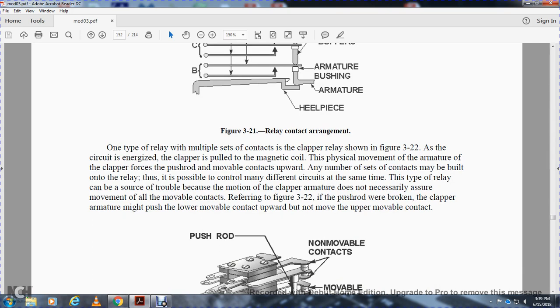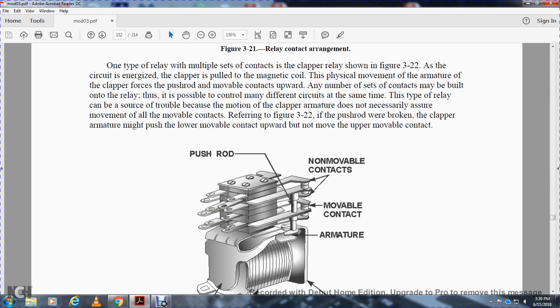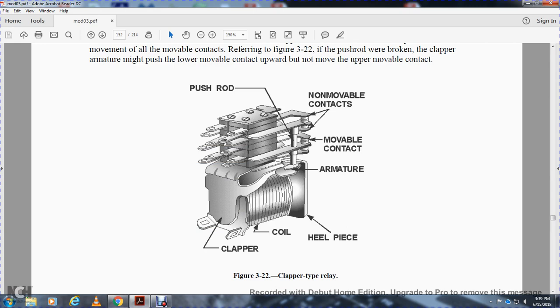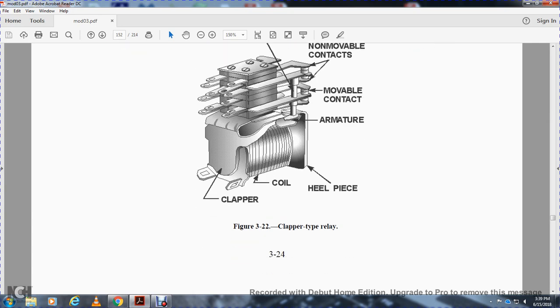This type of relay can be a source of trouble, lost motion, where the motion of the clapper armature does not necessarily assure the movement of the movable contacts. Refer to figure 3-22. If the push rod were broken, the clapper armature might push the lower movable contact upward, but not the upper movable contact. Figure 3-22 shows the clapper, coil, heel piece, armature, movable contacts, non-movable contacts, and push rod.